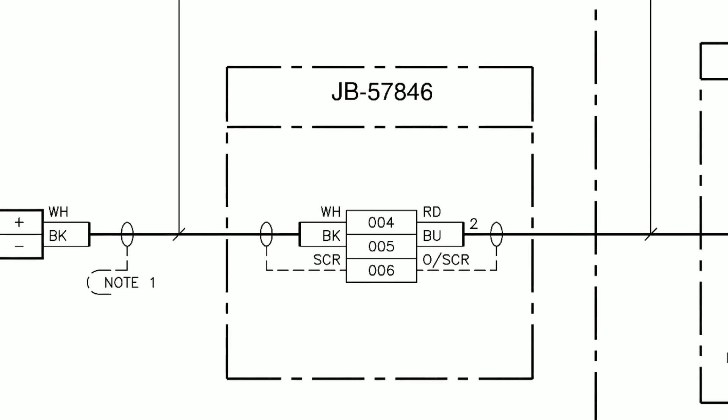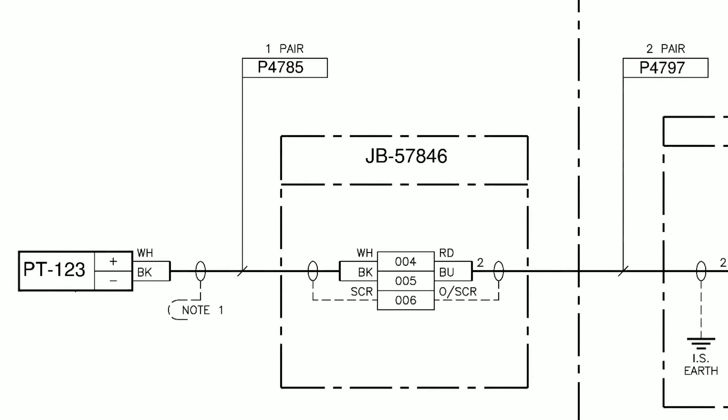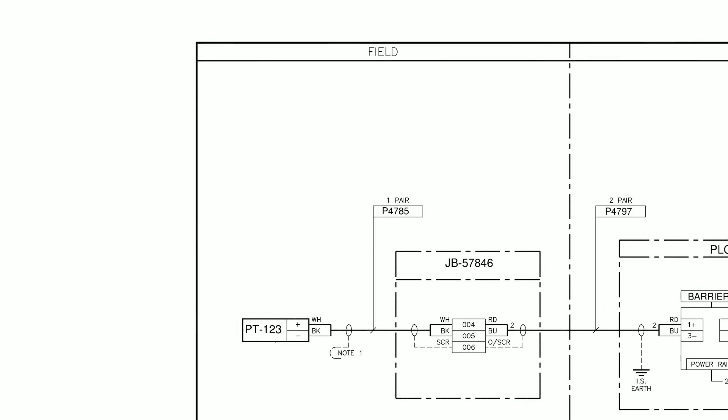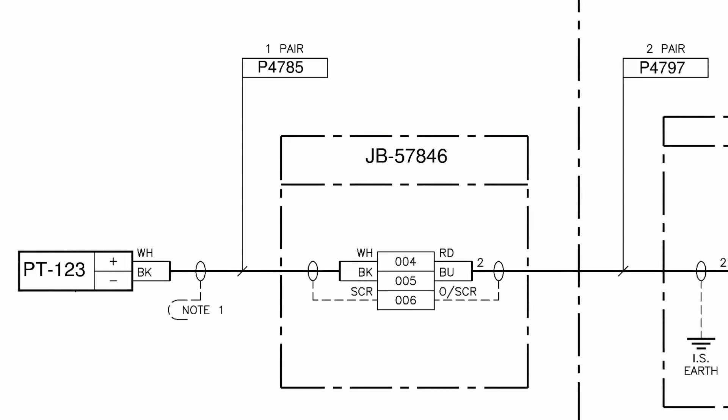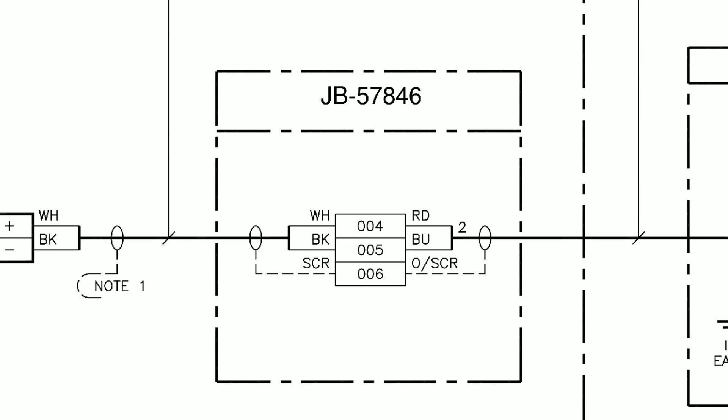We can see the cable connects to junction box JB57846 that is located in the field. Here the cable terminates to terminals 004 and 005, and the screen to terminal 006 within the junction box. This is the sort of information that is required for calibration and any testing you might have to do on the equipment. It gives you the exact terminals where you are going to be putting your test equipment, so it's important to understand how that's working.